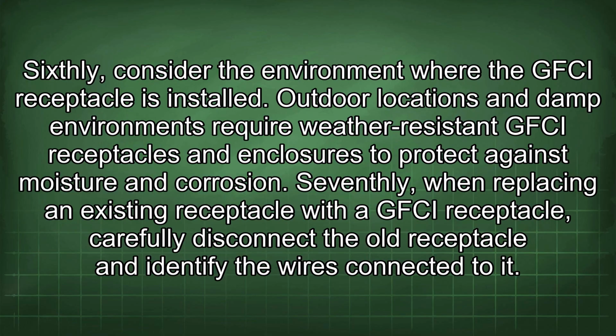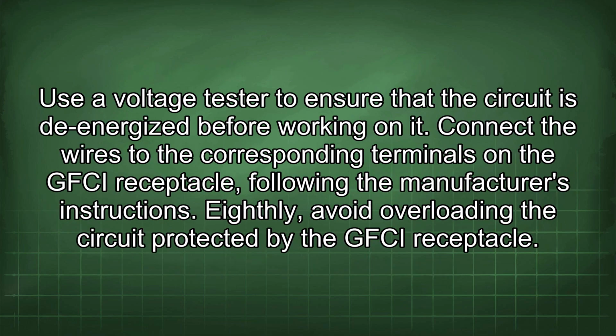Seventhly, when replacing an existing receptacle with a GFCI receptacle, carefully disconnect the old receptacle and identify the wires connected to it. Use a voltage tester to ensure that the circuit is de-energized before working on it. Connect the wires to the corresponding terminals on the GFCI receptacle following the manufacturer's instructions.